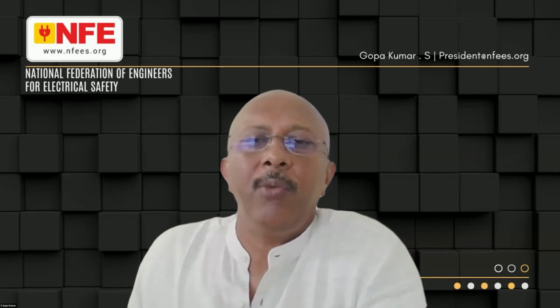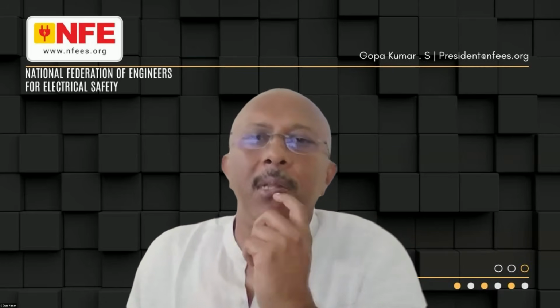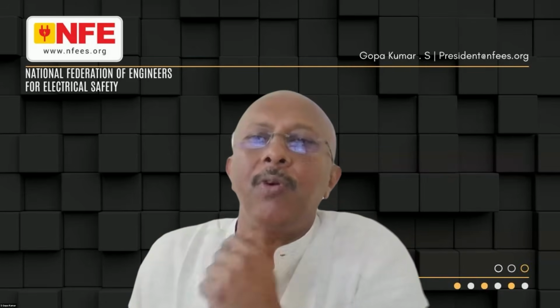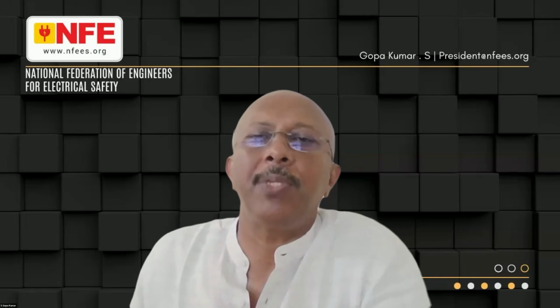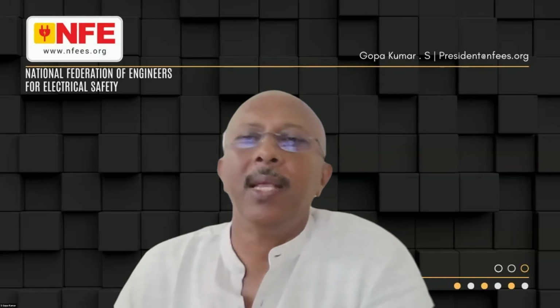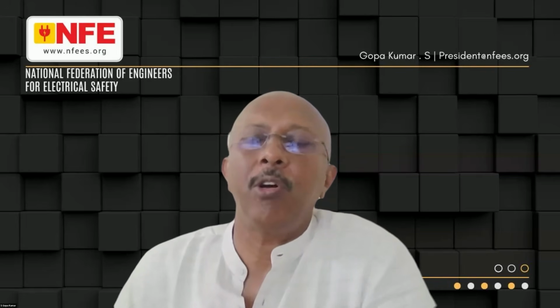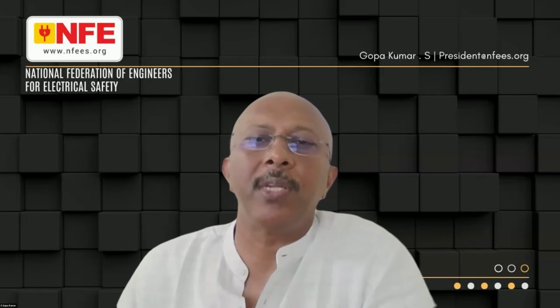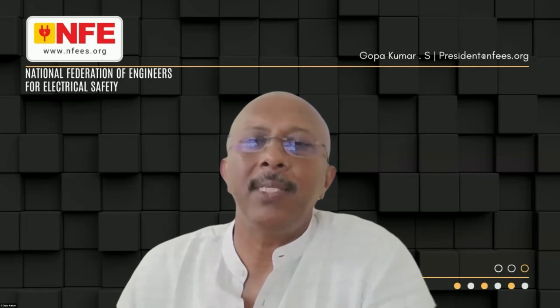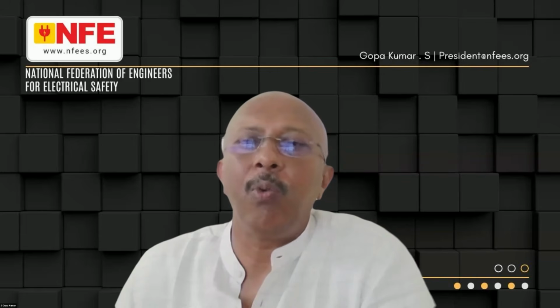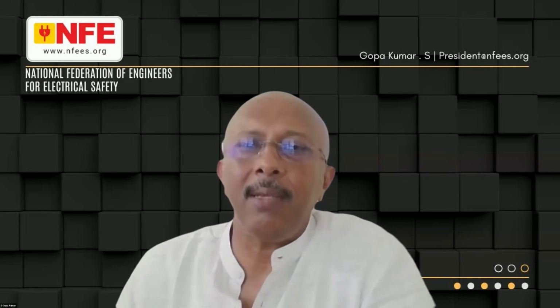So again, a question from Mr. Sunil Kumar. Suppose the hospital 11 kV transformer location is very near to a substation with high fault MVA, then if a short circuit occurs on the hospital transformer location, a huge fault current will be pumped into the hospital location. For dissipating such huge fault current and for limiting the touch and step potential, how will a single earth manage the situation? I don't know what you mean by single earth.